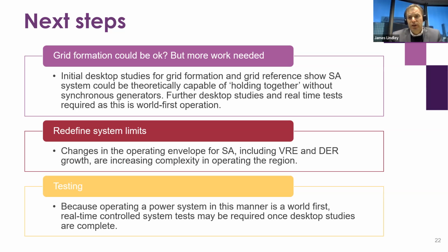Initial work has shown it looks like it can be done, and the on-paper results indicate we can maintain grid formation in the state with those synchronous condensers and high inertia and grid following inverters. But we've still got a little more to do there just to make sure.